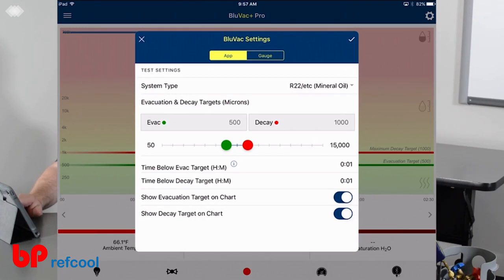I also have my time below target times here. Both of these are set at one minute. I'm going to hold the evacuation below 500 for a minute, and I'm going to allow it to decay for a time of one minute. Typically, these would be set for 10 minutes. But because we're doing the video for the sake of time, I'm allowing it to do these processes a little bit faster.